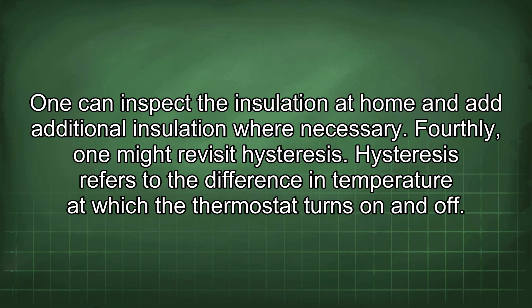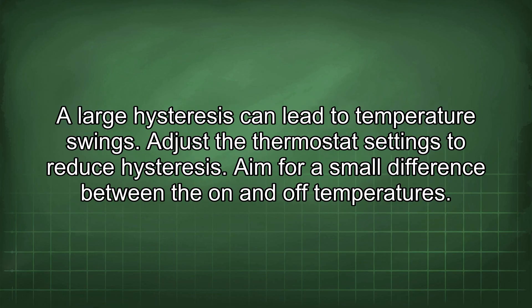Fourthly, one might revisit hysteresis. Hysteresis refers to the difference in temperature at which the thermostat turns on and off. A large hysteresis can lead to temperature swings. Adjust the thermostat settings to reduce hysteresis, and aim for a small difference between the on and off temperatures.